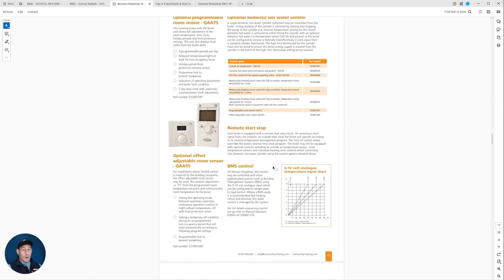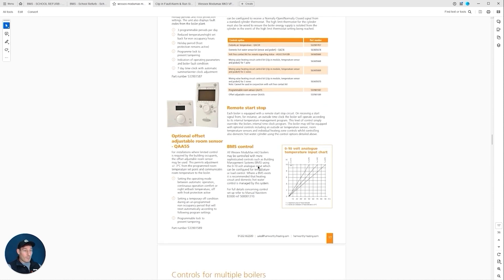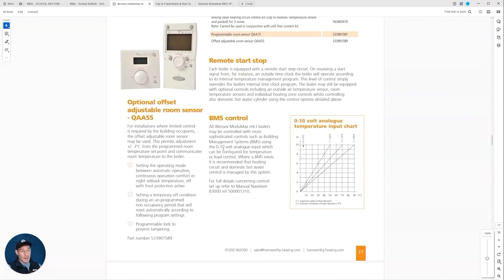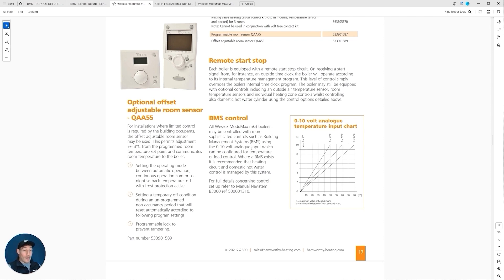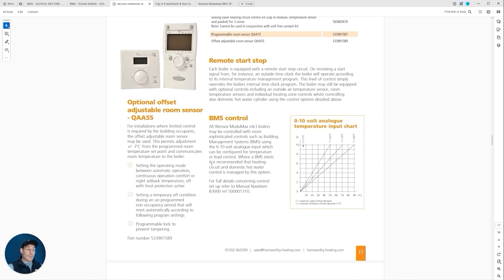This is talked about in the spec, but just on the tech manual here I want to bring your attention to this BMS control section. All Wessex ModuMax boilers may be controlled with more sophisticated controls such as building management systems using the 10 volt analog input which can be configured for temperature or load control. Where a BMS exists, it's recommended that heating circuit and domestic hot water control is managed by this system.